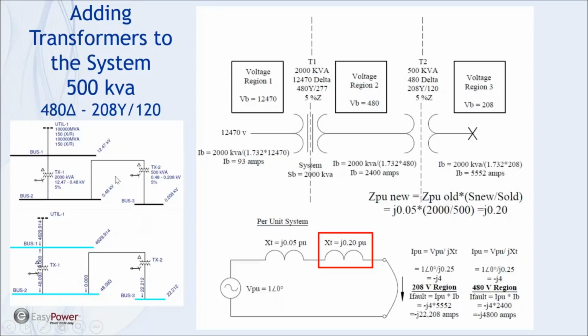Okay. Now, when we do that in EasyPower, we get the same thing: 2,000 kVA, 12,470 to 480, 5% Z, and a 500 kVA. And on the fault current, we get 22,212 with that guy.